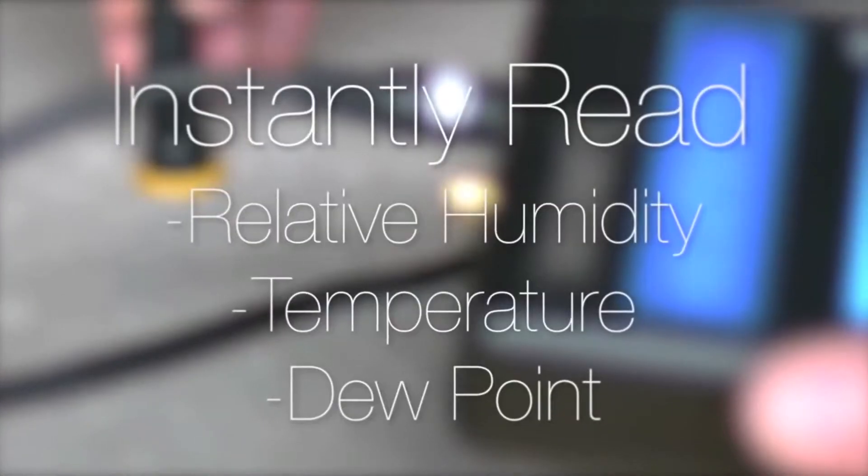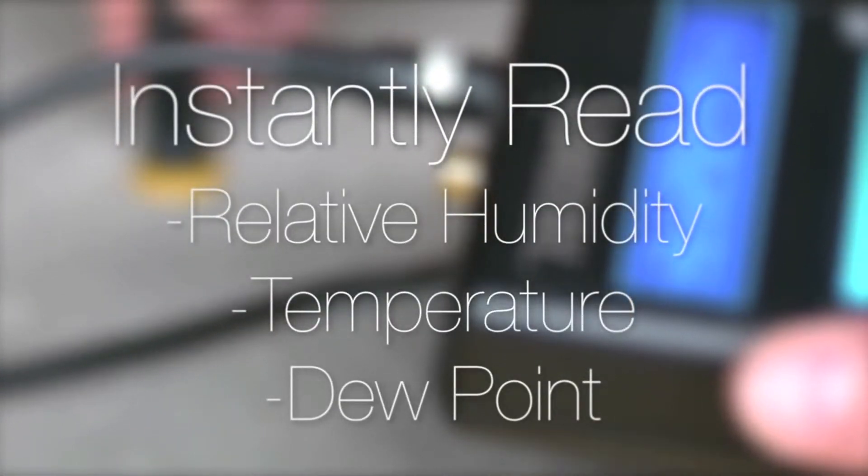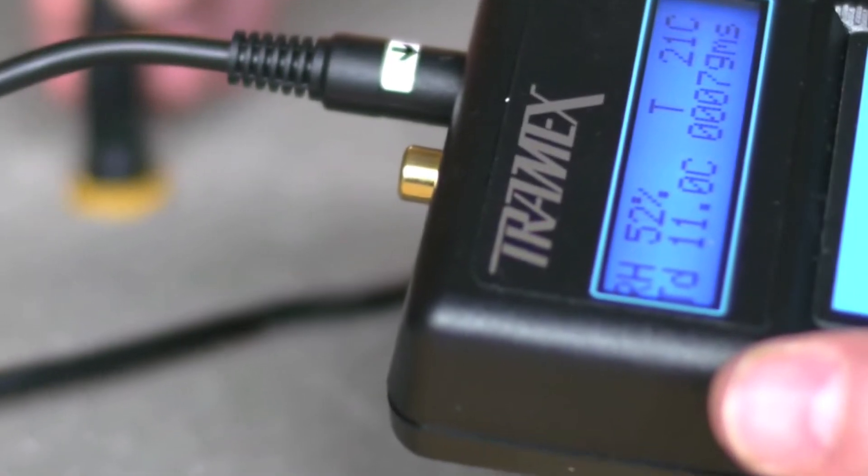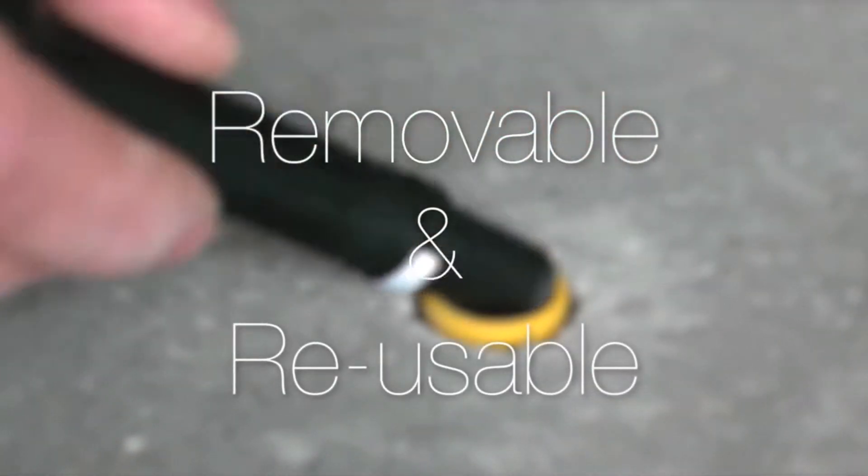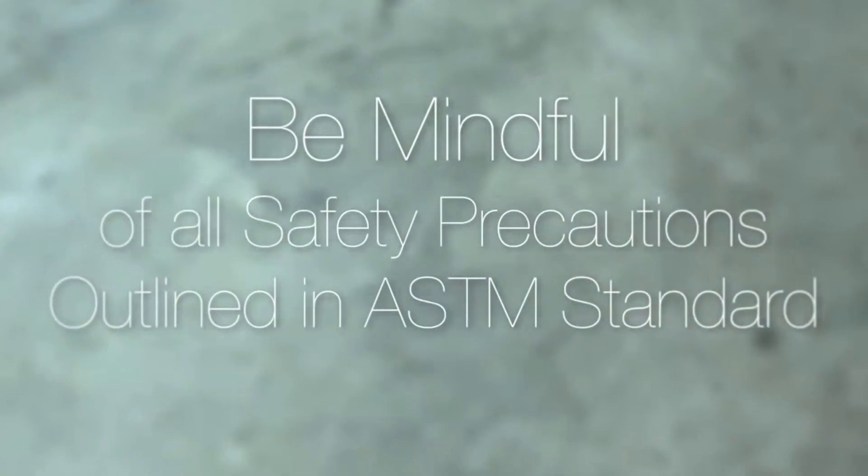When taking readings, plug the interface into the Hygroi probe and instantly read the relative humidity, temperature and dew point simultaneously on the clear display. When testing is complete, the Hygroi probes can be removed with the extraction tool and used repeatedly. The user must be mindful of all the proper safety precautions as mentioned in the ASTM standard.